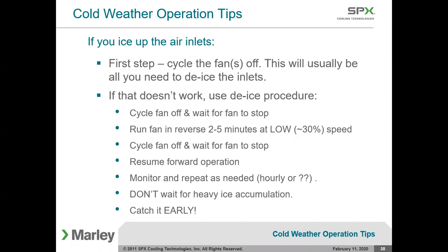We were looking at cold weather operating tips to de-ice your cooling tower if it happens to get iced up. I think we went through most of this, but we can hit it one more time. The first thing would be to just cycle the fans off. That warm water, you probably got 50, 60, 70, 80 degree water, maybe even hotter, being introduced at the top of the tower. That falls down the fill, hopefully on the outside, preferentially, and can melt any ice buildup in hopefully a fairly short period of time. So that would be option one.